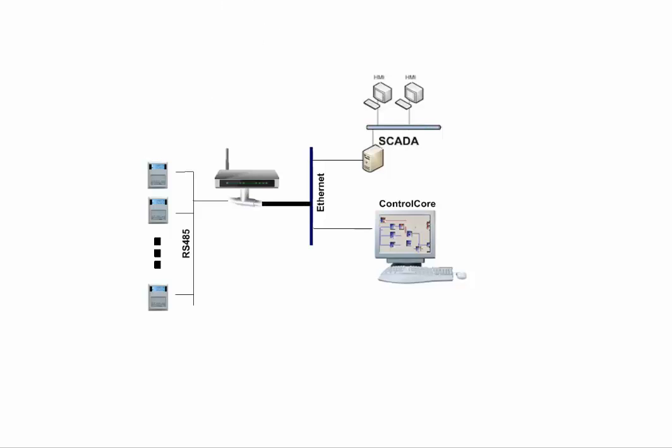The network controller, or a PC running NC server, solves these problems once and for all. Unlike the RS-485 or the gateway, the network controller does not simply relay messages down the RS-485 line and relay the device's response back. Instead, the network controller handles all necessary scanning itself and keeps in memory a database of all the blocks values for every device that it is scanning. When an application makes a request to get values from a device, the network controller responds immediately with the values it stored in its database, and it is constantly scanning these devices, updating these values.